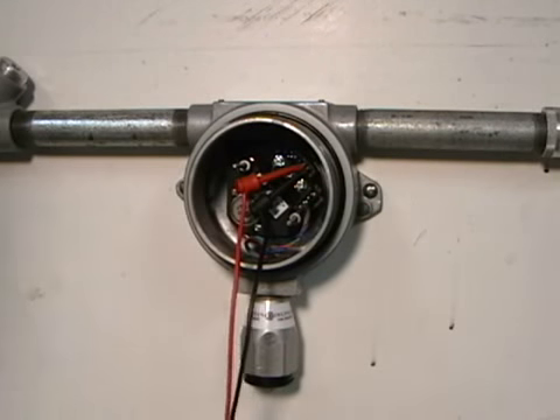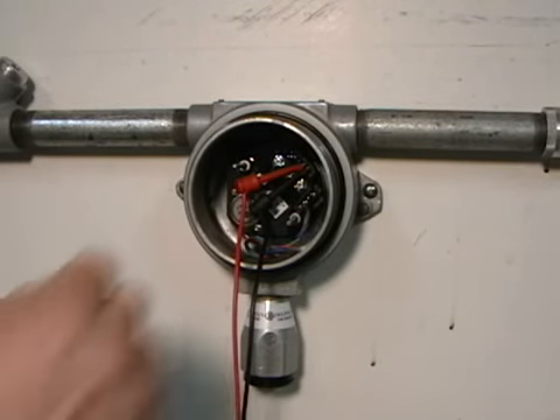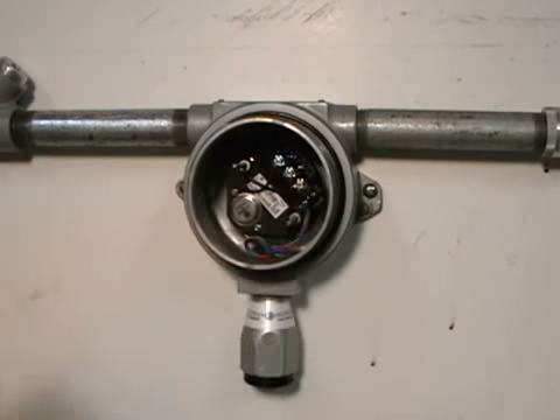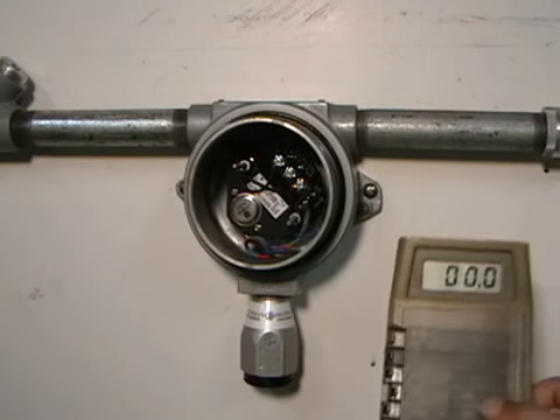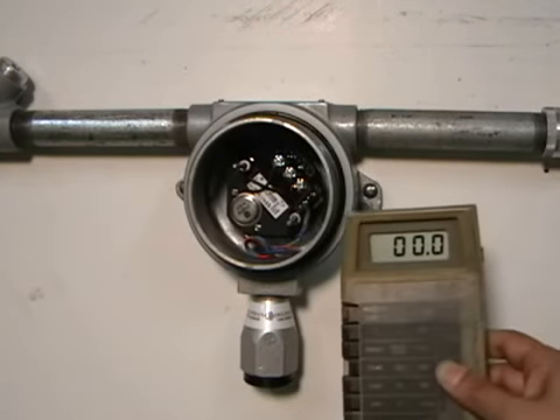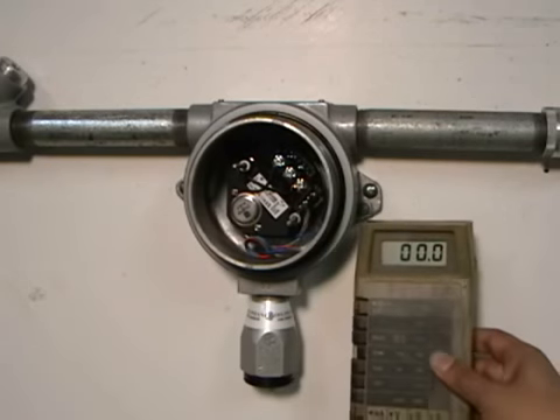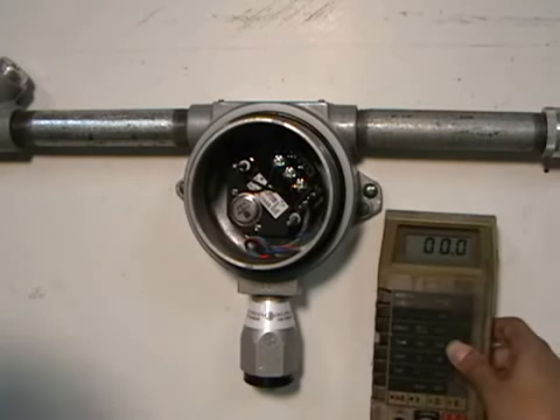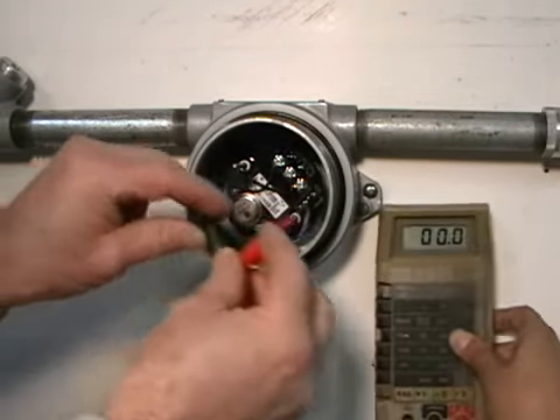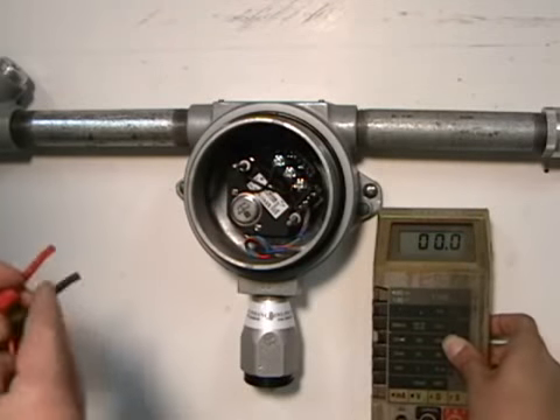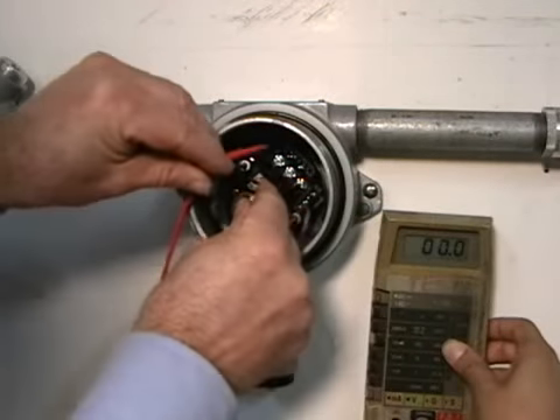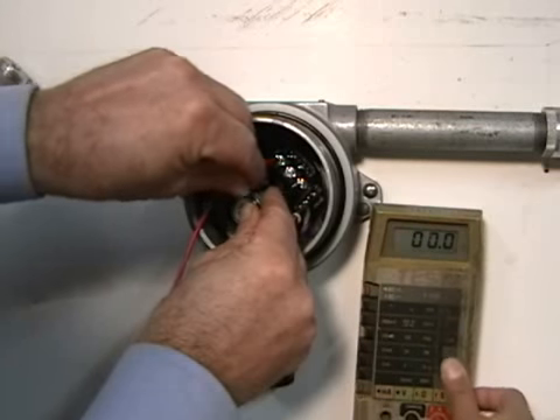The next test that can be performed is the voltage tests. This can actually be performed first if you suspect there might be a power issue, such as a bad power supply or battery backup system. With the DVM on volts, place the probes on the plus and minus terminals of the transmitter. Although we spec out a 24-volt DC power supply, voltages from 20 to 28 volts DC are acceptable.